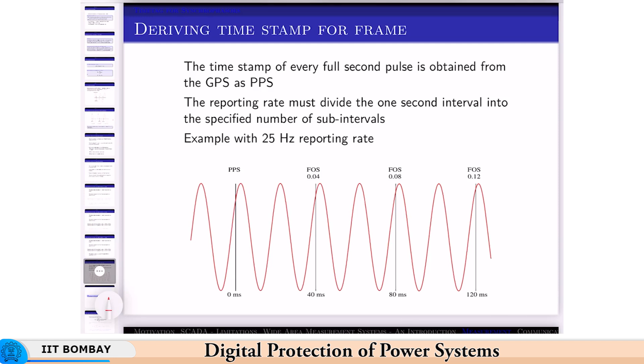For a 25 hertz reporting rate, you have FOS indicators at every 40 milliseconds. If it was a 50 hertz reporting rate, the first FOS would have been at 0.02, that is 20 milliseconds. But since we are talking about 25 hertz rate, you have FOS at 0.04, 0.08, 0.12, 0.16 and so on.